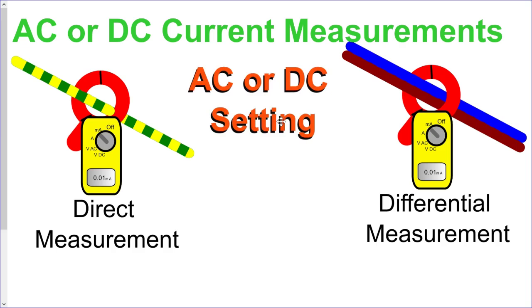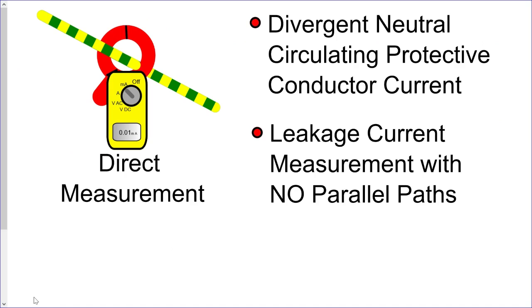Okay. As well as that, we need to make sure that we're measuring AC or DC, depending on what it is that we're looking for. So either that alternating current for your leakage or your DC setting to work out what the DC components are flowing back into your RCDs. Okay. So direct measurement, when would we normally use direct measurement?